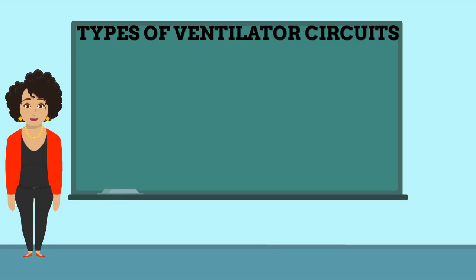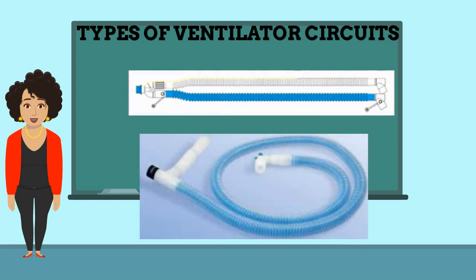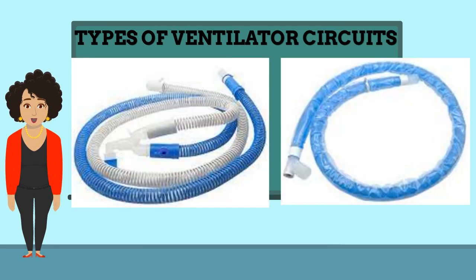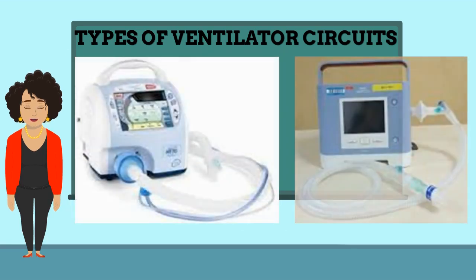Ventilator circuits are double or single limb. Both circuits can have a water trap. Double limb can have a water trap on one or both tubings. They can both have heated wire, and single limb can have an active or passive tubing.